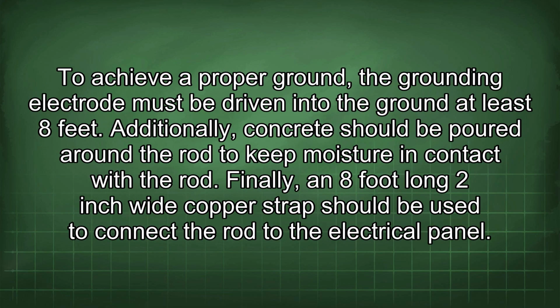To achieve a proper ground, the grounding electrode must be driven into the ground at least 8 feet. Additionally, concrete should be poured around the rod to keep moisture in contact with the rod. Finally, an 8-foot long 2-inch wide copper strap should be used to connect the rod to the electrical panel.